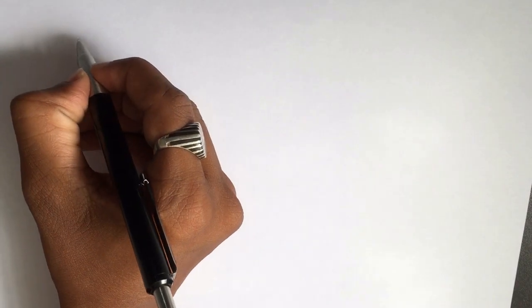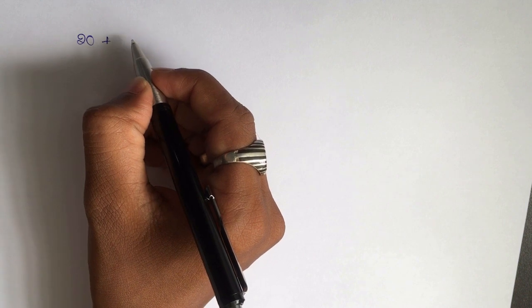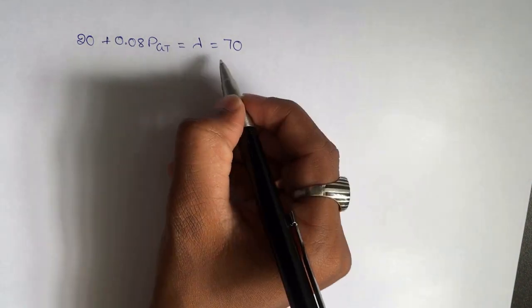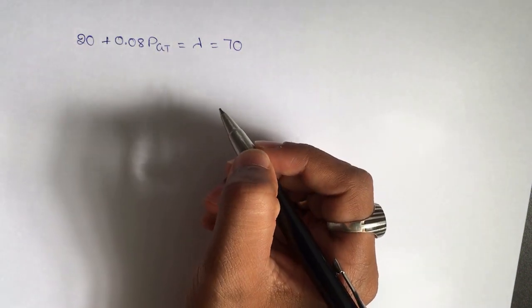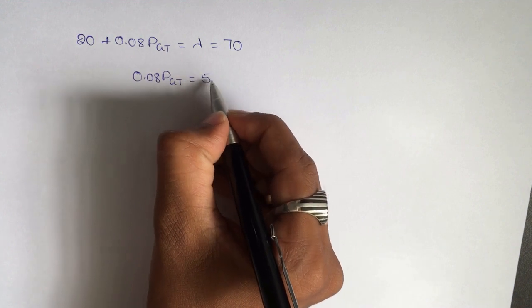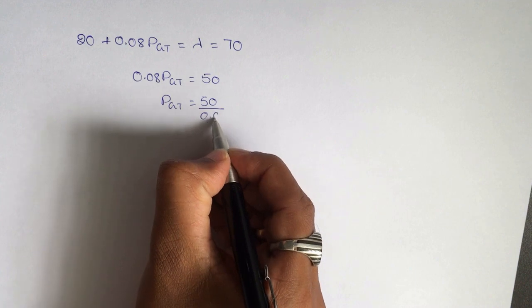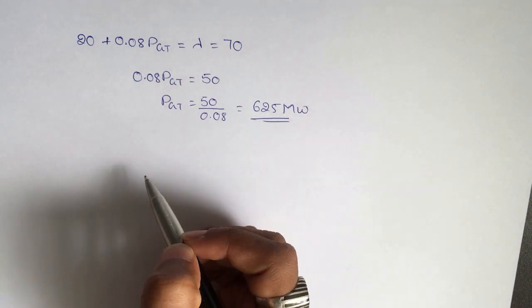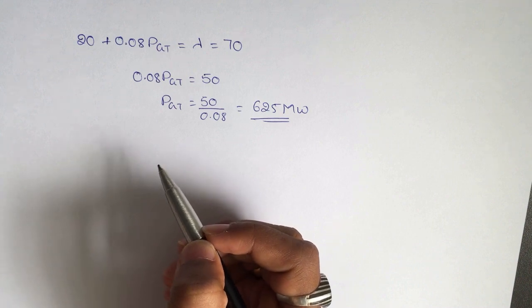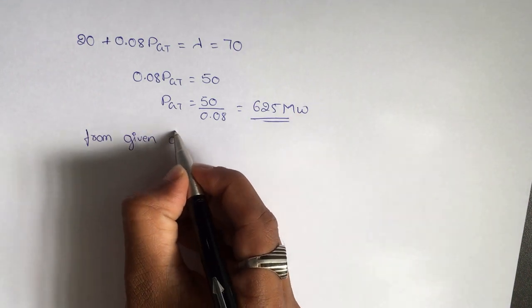Differentiating F_T with respect to P_GT gives: 20 + 0.08·P_GT = lambda = 70. Solving: 0.08·P_GT = 70 − 20 = 50, so P_GT = 50 / 0.08 = 625 megawatt. We now have the value of P_GT.